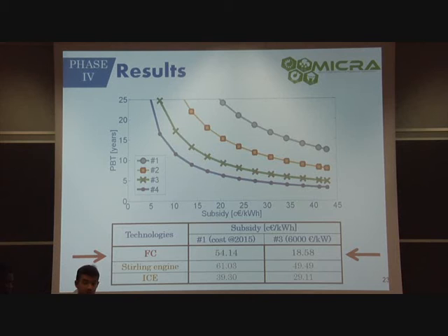This calculation is repeated for four different values of capital cost. With capital cost number one — meaning current cost, 2015 cost — the internal combustion engine needs the smallest amount of subsidy, then fuel cell, then the Stirling engine. But with a cost of 6,000 euro per kilowatt, the fuel cell needs the smallest amount of subsidy, then internal combustion, then the Stirling engine. Assuming that in the next 10 to 15 years micro-cogeneration will reach full commercialization and costs will decrease below 4,000 to 6,000 euro per kilowatt, the result of the techno-economic analysis is that the fuel cell is the most promising solution.